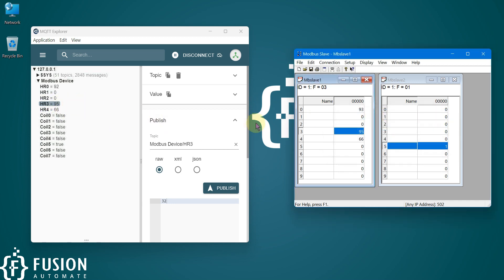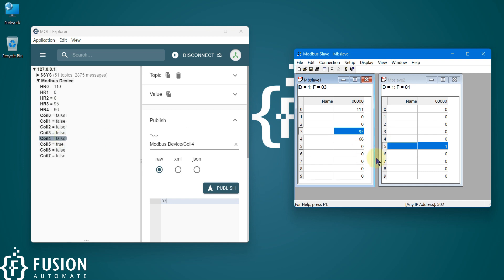So it's a bi-directional gateway: Modbus data is read by Node-RED and published to the MQTT broker. From any MQTT client you can read that data, and if your MQTT client updates any topic, Node-RED will get the topic and write that data back to the Modbus TCP device. You can also do the same for your Modbus serial device, which we will cover in the next video.